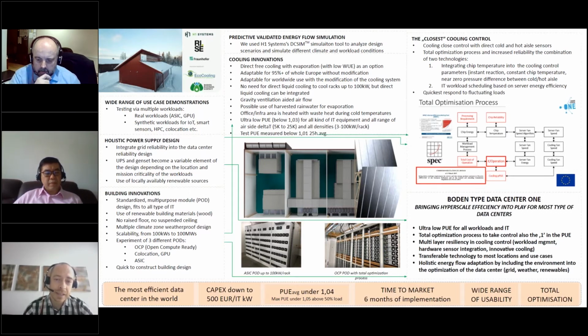So this is the Boden type data center. You can Google it and find details, where we were actually able to push the cooling PUE below 1.01, below 1% only. Of course, you can say it's in Sweden so it's cold, it's easy. But that's not actually that easy — even in Sweden, reaching a cooling PUE below 1% is not easy to achieve.